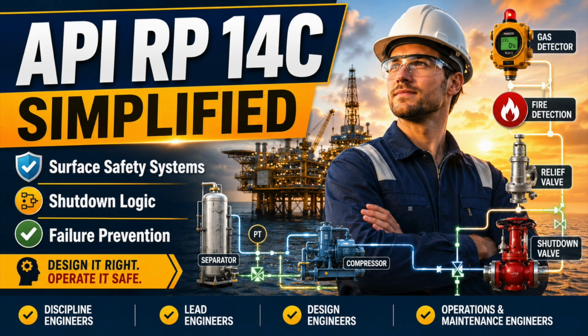What is the governing relief scenario? Where does the relieved material go? What happens upstream when this valve closes? What flare load appears when this system blows down? What position does every final element take when utility power is lost? Where is the equivalent protection when a device has been omitted? If the team cannot answer these questions clearly, the design is not finished.